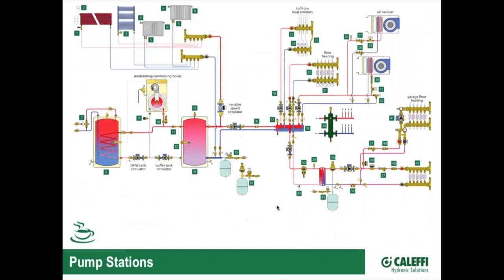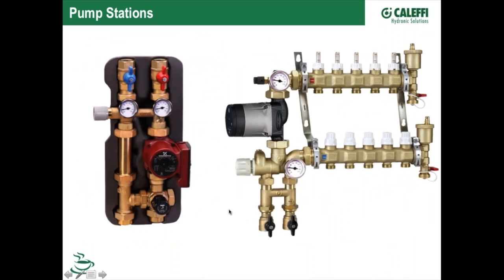So, pump stations. We've got the ability to offer mix stations that can either go on our HydroLink, which I'll show you here in a minute, pipes right onto it. If you want to pipe into this from a primary loop, or if you want to have this built right onto a manifold, we can offer this solution here too, where now we've got the mixing right at the manifold, the pumping right at the manifold, the gauges, and the flow or balancing devices built right on the manifold. So this comes out of the box, you supply your temperature to it from your heat source, your boiler, you've got the mixing, the pumping, the balancing, and the zoning down here. We take these caps off, we put actuators on. So this becomes a device that can solve all those functions right out of the box for you.